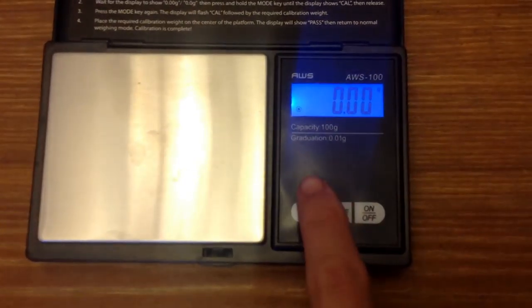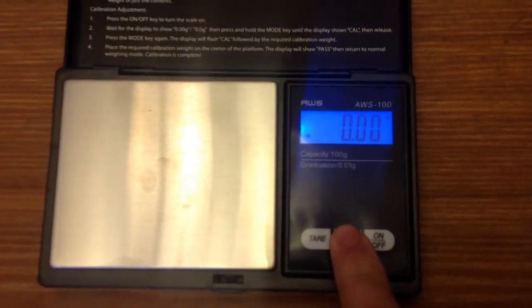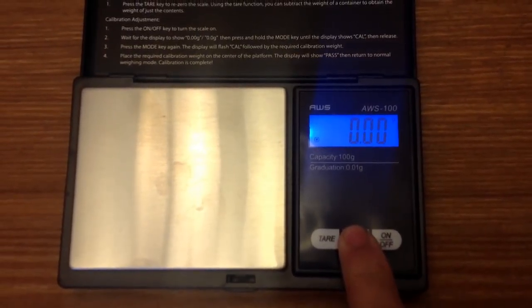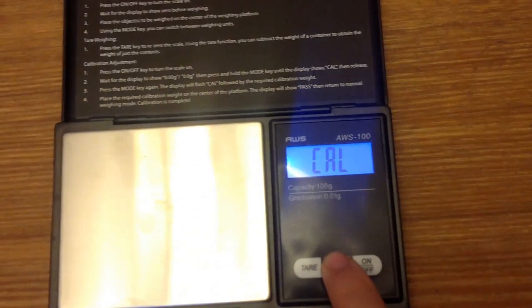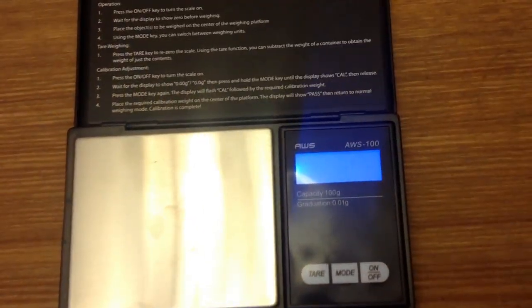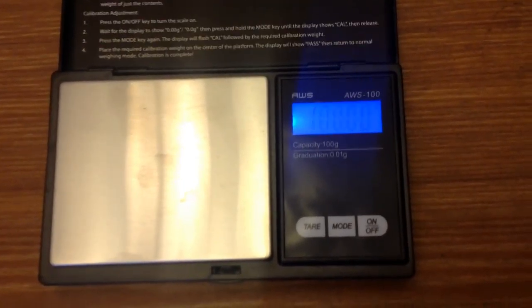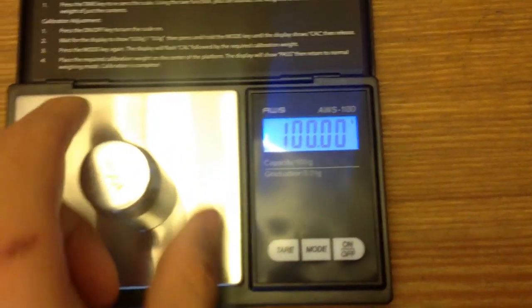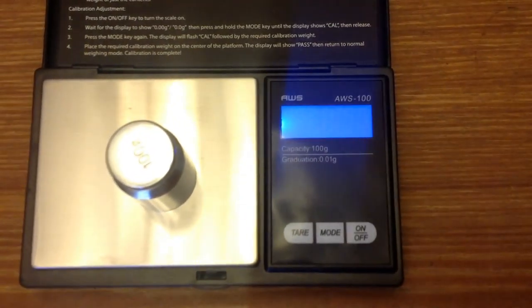So once again, how to calibrate it, hold mode down. So you see that. Click it once. So it'll start flashing. And it'll show you the required weight to calibrate it with. So I'll put my 100 gram calibration weight on.